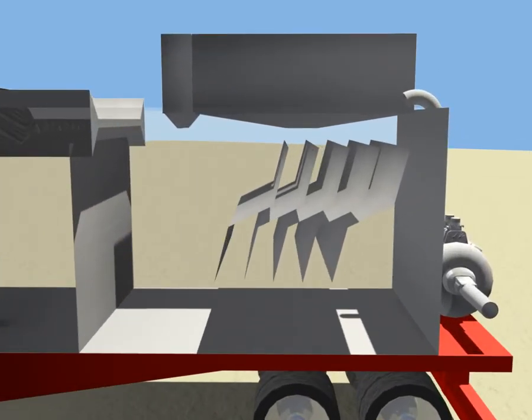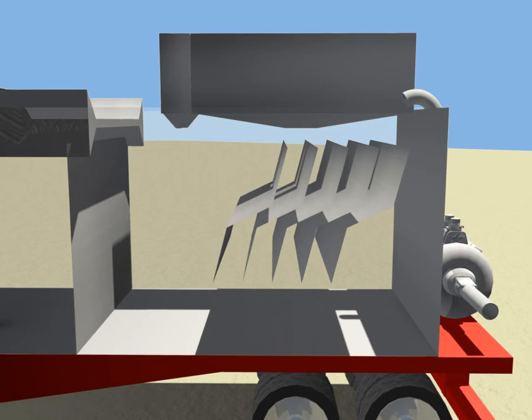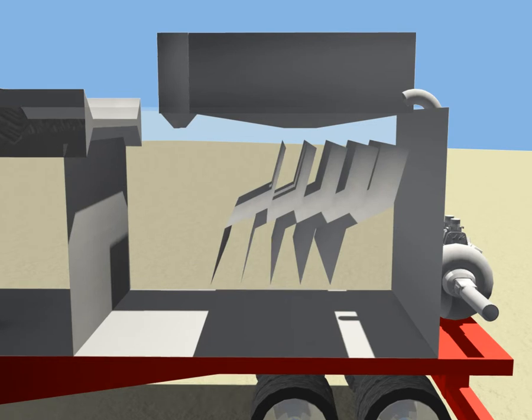5,000 barrels of wastewater per day of about 50,000 parts per million TDS will be processed. The residence time for the combined preconditioning tanks is about 1 hour. The mixing tank with baffles will promote mixing of chemical additives with the wastewater to facilitate the precipitation of divalent cations and heavy metals. Flocculants and dissolved oil clarifiers will be added to aid in the flocculation of precipitates and the handling of oils and greases.